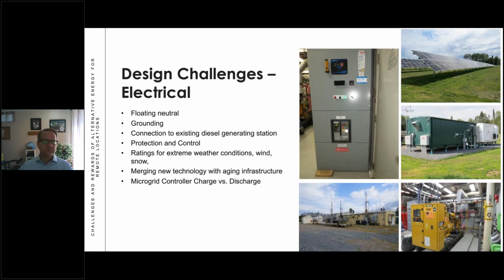Other challenges with this location were the extreme cold temperatures. We had to implement a cold starting energization procedure for the transformers and integrate that into the protection and control design of the microgrid. Ratings for those extreme weather conditions were also a challenge too, with the conditions with the wind and the snow and the low temperatures. So inverters, sensors, and transformers and other equipment had to be carefully selected to meet those needs.